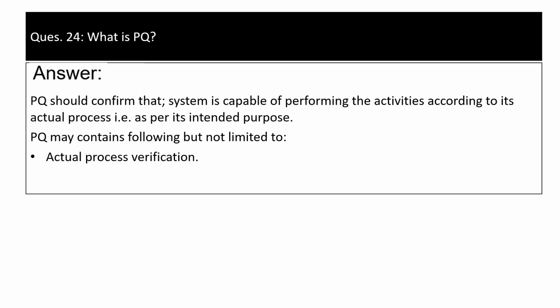Question number 24, what is PQ? The answer will be, PQ, that is performance qualification, should confirm that the system is capable of performing the activities according to its actual process, that is as per its intended purpose. PQ may contain the following but not limited to the actual process verification.